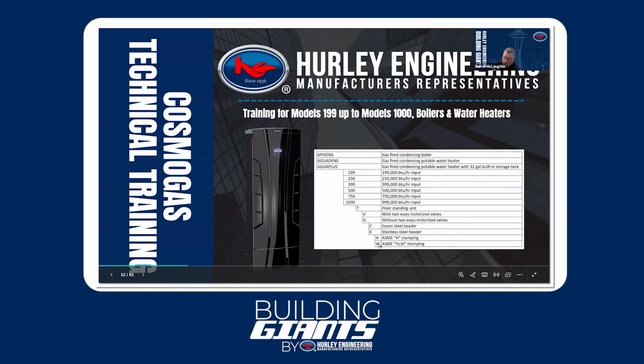So the heat exchangers are not interchangeable. They're actually ASME stamped differently depending on if it's a heating or a hot water application. Just keep that in mind in case you have both at your location, you've got to keep those straight. Also, there is a motorized valve option that we'll talk about and I'll show you in a little bit. So you can get them with or without motorized isolation valves on each of the heat exchangers.